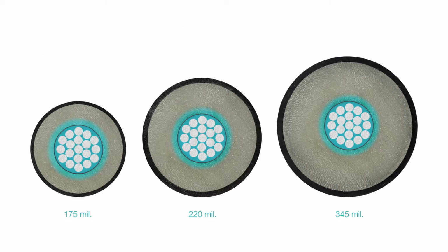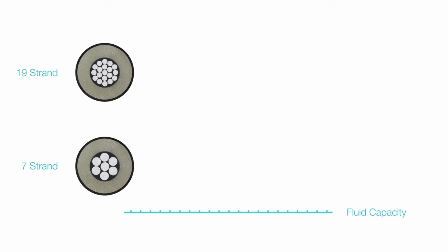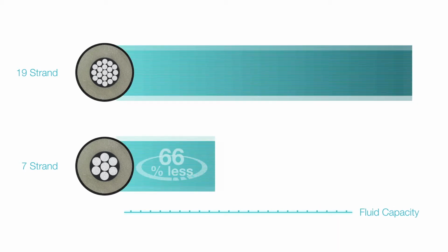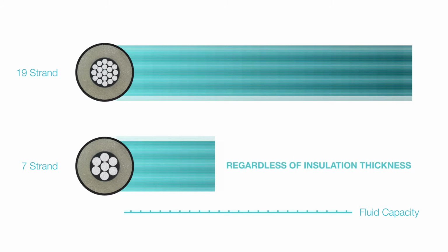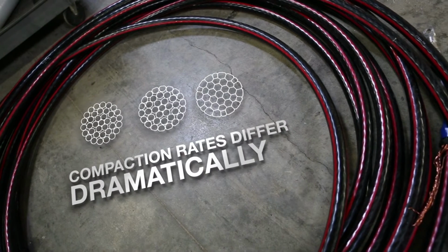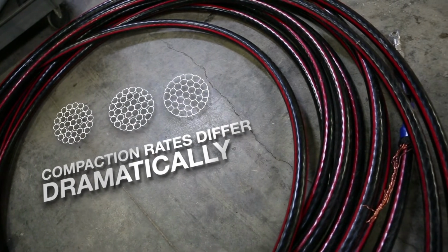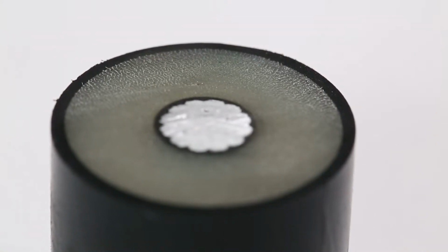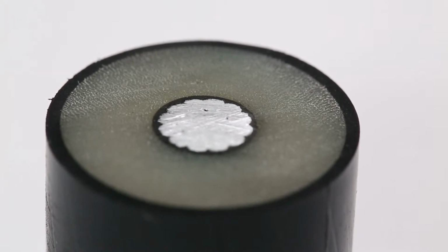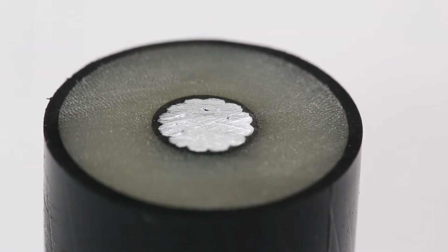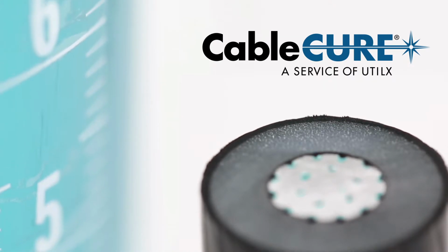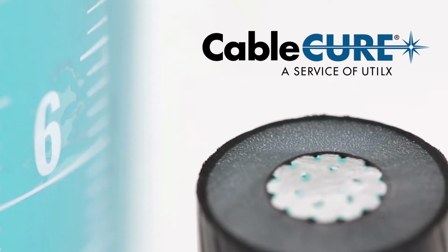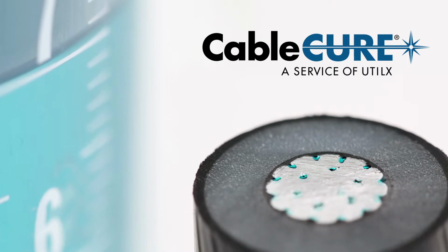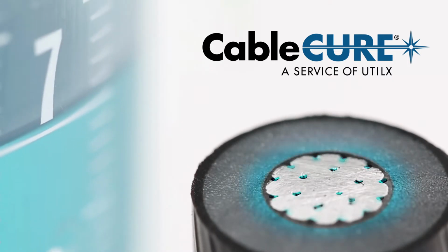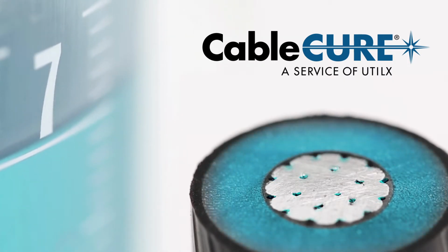It gets more complicated. For example, a 7-strand 1/0 cable can contain 69% less fluid than a 19-strand 1/0 cable, regardless of the thickness of its insulation. Finally, compaction rates differ dramatically. Therefore, it is not possible to rely on the interstitial space between the conductors as an appropriately sized reservoir for rejuvenation fluid. The UtilX CableCURE process does not assume that the tiny space between the conductor strands can be used as a reservoir. We view it as nothing more than a conduit for transferring fluid to the cable's insulation.